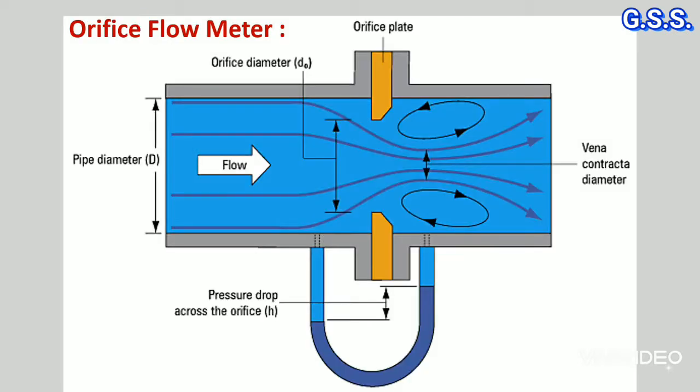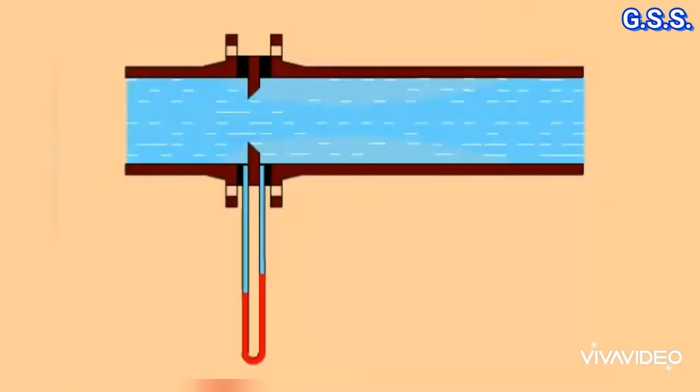In orifice flowmeter, an orifice plate is inserted in a pipeline between two flanges. The orifice plate has a round hole at the center. This hole makes a constant throttling and generates differential pressure. This differential pressure is proportional to flow rate and is used to determine volume flow rate through the pipeline.